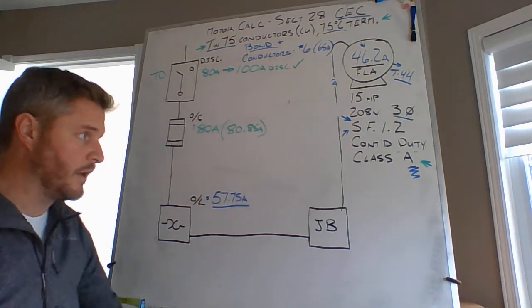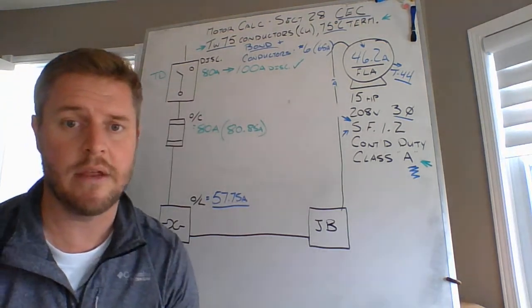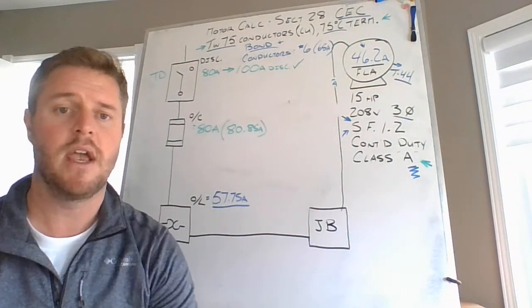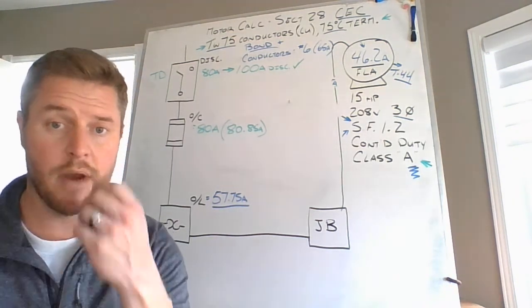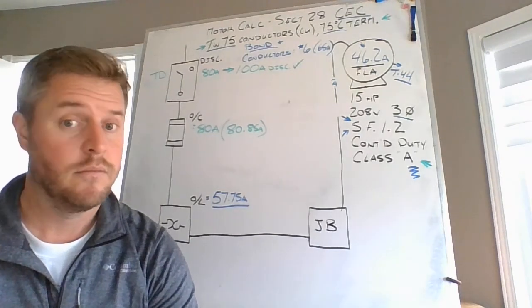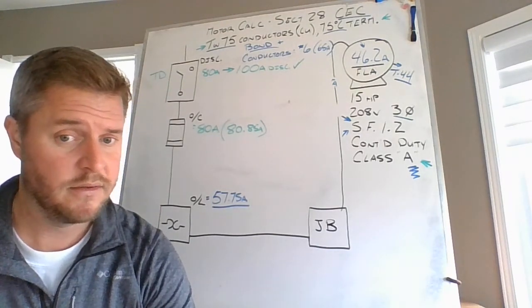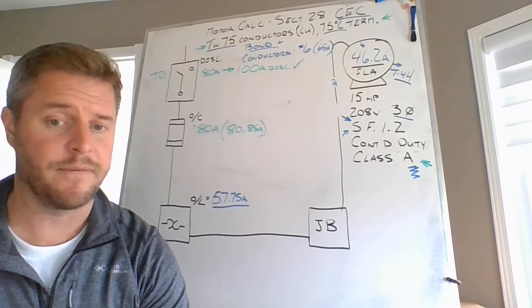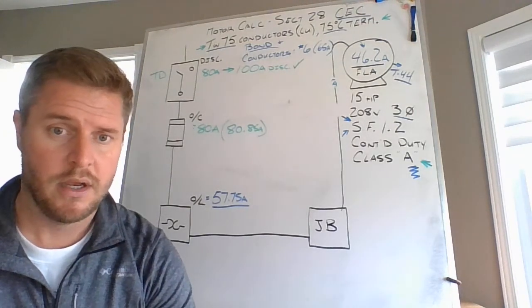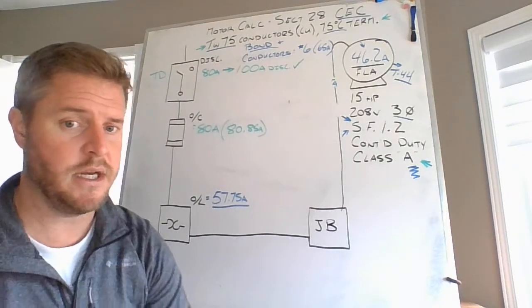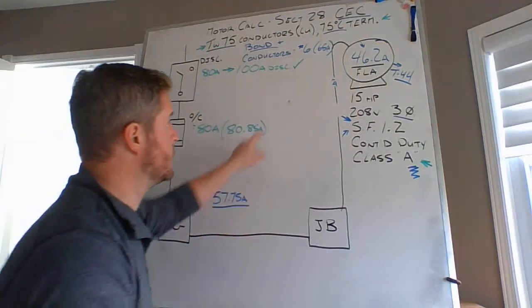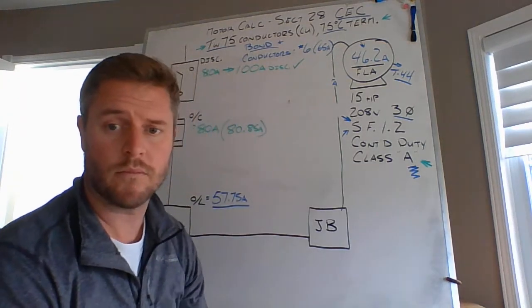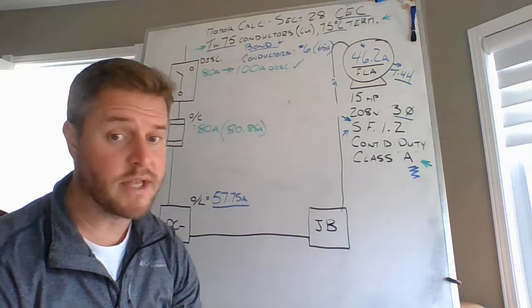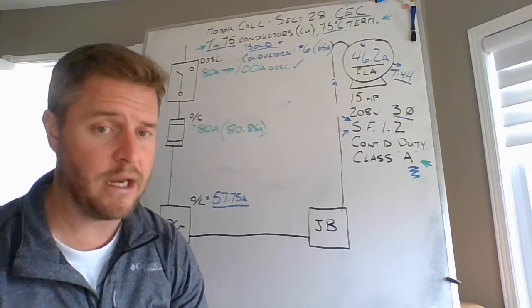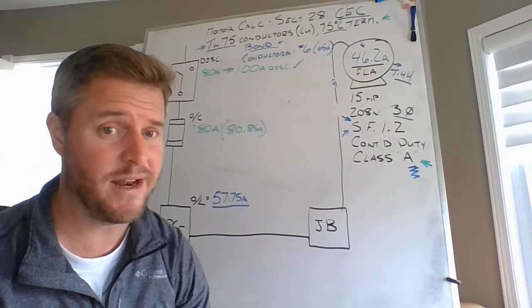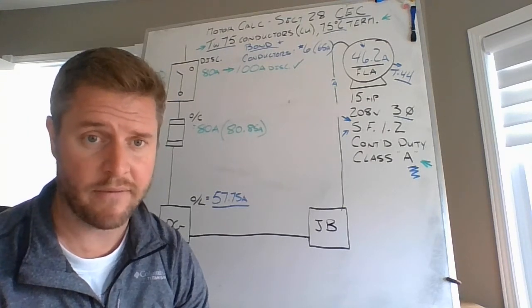So if you've done this calculation correctly, you will see that yes, you are going to terminate number 6 TW75 conductors into a 100 amp disconnect with 80 amp time delay fuses. You're going to set your overloads to 57.75 amps, and now you possibly might see that your overloads are actually protecting your conductors. Because that 80 amp overcurrent device isn't doing anything for your conductors. Your conductors are only set and rated for no more than 65 amps.